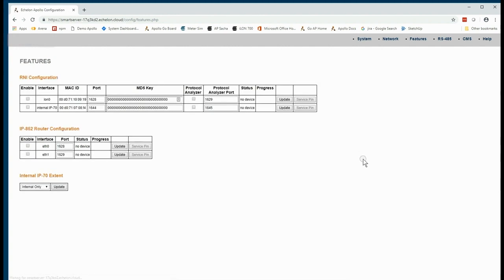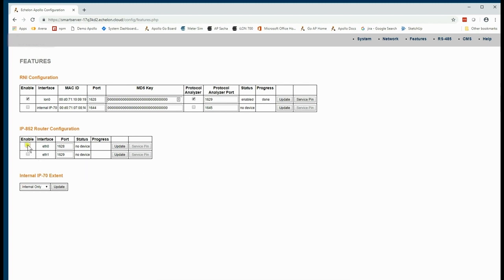In the Features tab, we can enable the different interfaces to use RNI. RNI stands for Remote Network Interface — an interface that is attached by IP. It is important to note that with each feature you enable, you need to lock it in by clicking the corresponding Update button. RNI interfaces are ones that are managed with LonWorks 32 interfaces in the control panel applet. It's here that we define the ports that are used and whether they're enabled or not.